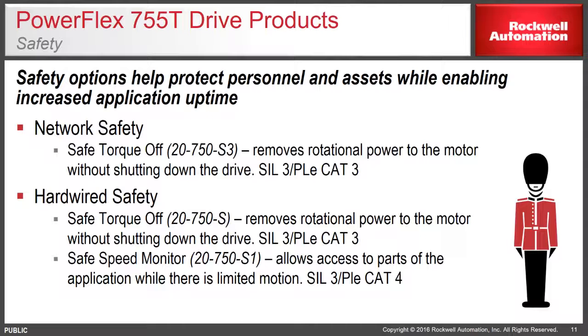We also support hardware safety with a safe torque off board, 20-750-S, which removes rotational power to the motor without shutting down the drive. Again, meets SIL 3, PLE Category 3. We also have safe speed monitor, 20-750-S1. Allows access to parts of the application while there is limited motion. Again, meets SIL 3, PLE Category 4.